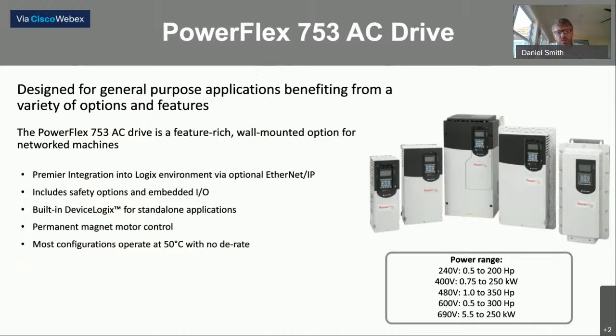Another big addition to the 750 series drives is the built-in DeviceLogix. The DeviceLogix is great in a lot of standalone applications where if you have a drive that needs to do some control, but you don't want to invest in a small PLC, 750 series drives have a small PLC built in. It can look at levels and analog signals and write some code just like if you were writing ladder logic or function block in a ControlLogix platform and have the drive do some controlling for you. Next slide.